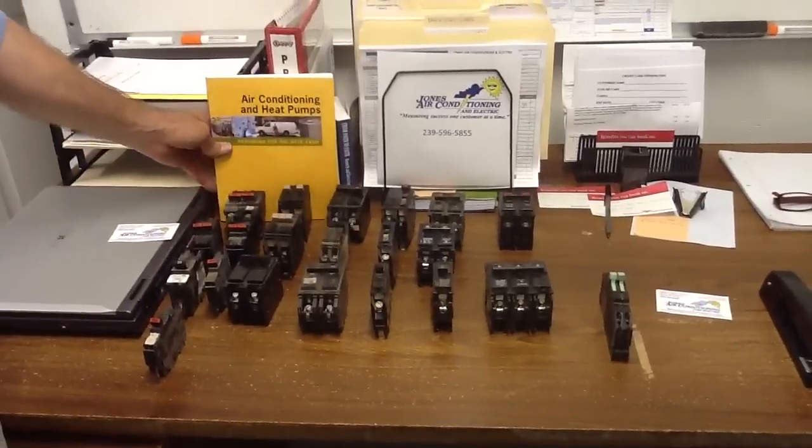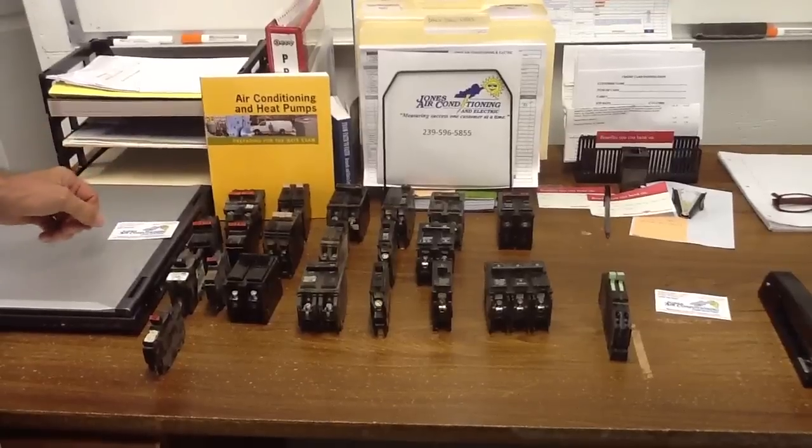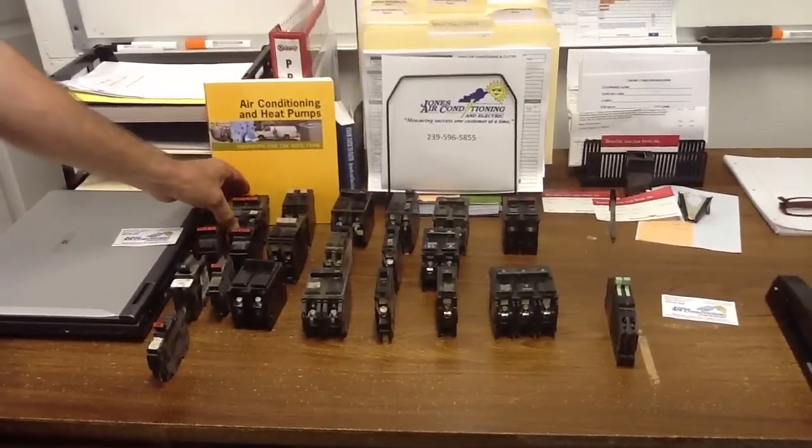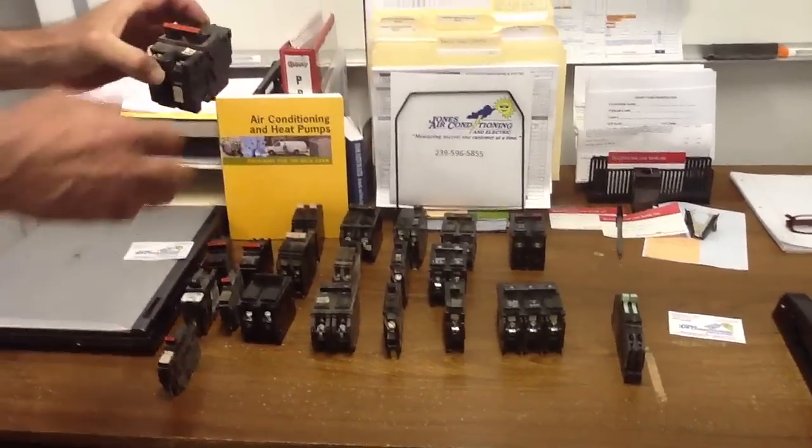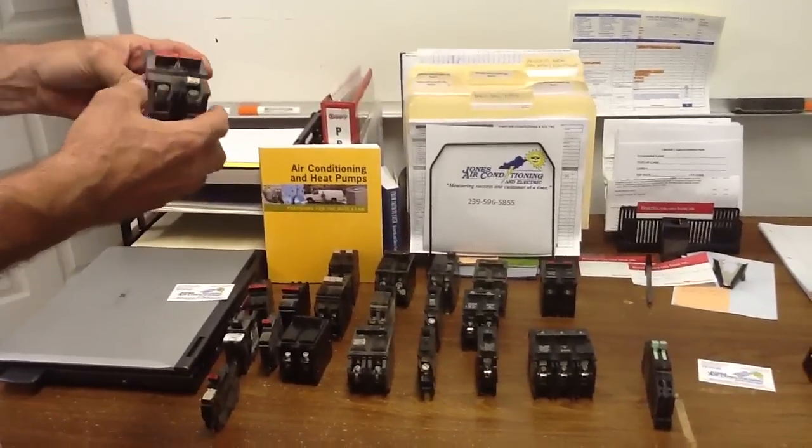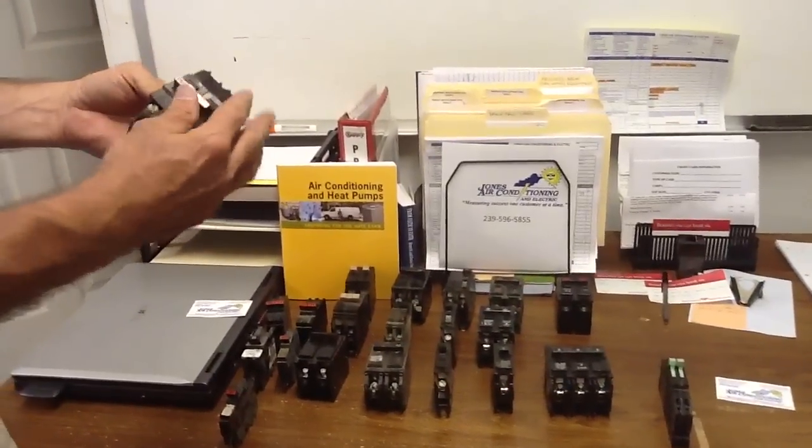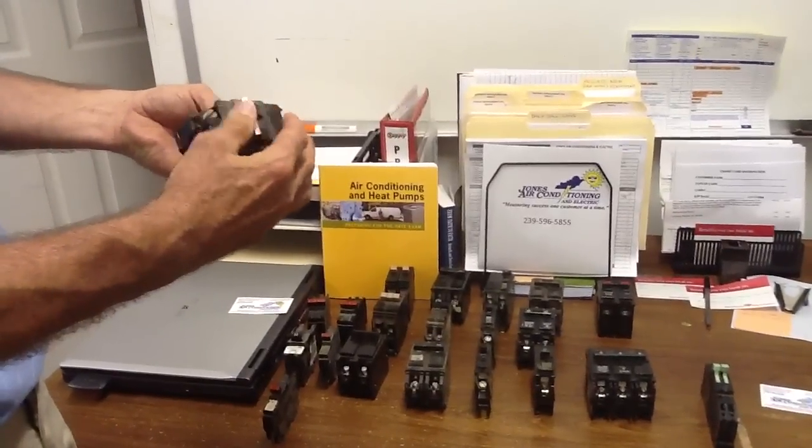We're going to talk today about different breakers that's on the market. The first breaker I'm going to pick up is a Federal Pacific. You look at the red markings here, it's very distinguished. They're very hard to open and close.